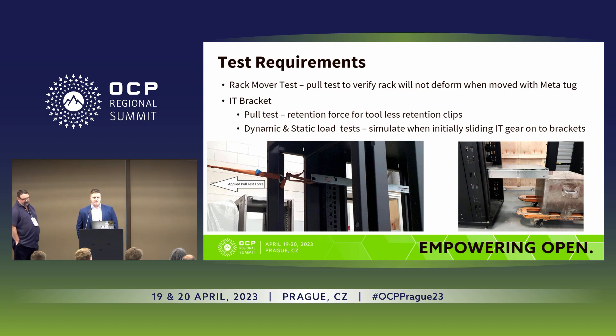As Glenn mentioned, we had some challenges and product updates throughout the development. One of them was the IT bracket. The image on the left shows a rudimentary but effective test we carried out, testing the pull-out force and ensuring that changes were effective and all the rails would stay fitted into the rack through normal use — making sure the rails aren't dropping out when equipment is removed, given that they're now tool-less. We also carried out a rack mover test using a Meta tug with a fully populated rack, doing a series of handling tests to move the rack around and ensure equipment engagement was maintained and the rack didn't distort throughout its normal life cycle.